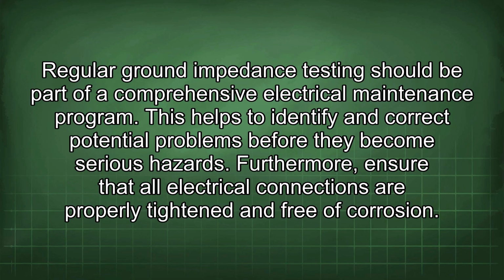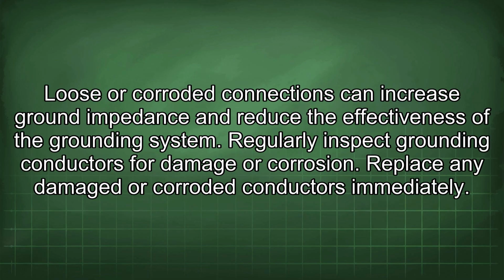Regular ground impedance testing should be part of a comprehensive electrical maintenance program. This helps to identify and correct potential problems before they become serious hazards. Furthermore, ensure that all electrical connections are properly tightened and free of corrosion. Loose or corroded connections can increase ground impedance and reduce the effectiveness of the grounding system. Regularly inspect grounding conductors for damage or corrosion. Replace any damaged or corroded conductors immediately.